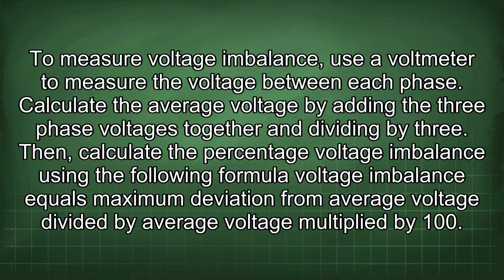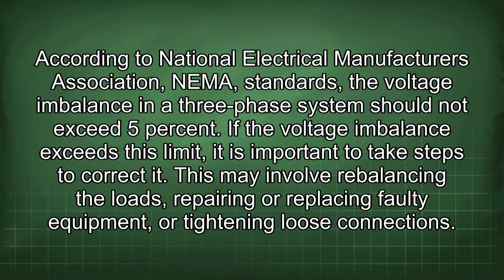Calculate the average voltage by adding the three-phase voltages together and dividing by 3. Then calculate the percentage voltage imbalance using the following formula: voltage imbalance equals maximum deviation from average voltage divided by average voltage multiplied by 100. According to National Electrical Manufacturers Association (NEMA) standards, the voltage imbalance in a three-phase system should not exceed 5%. If the voltage imbalance exceeds this limit, it is important to take steps to correct it. This may involve rebalancing the loads, repairing or replacing faulty equipment, or tightening loose connections.